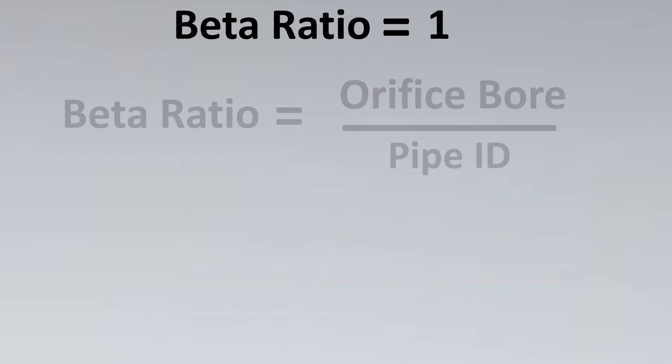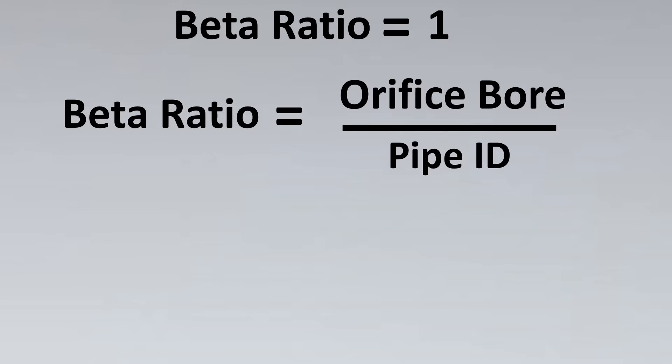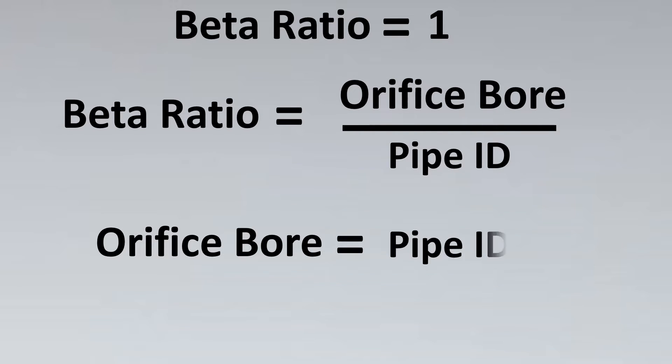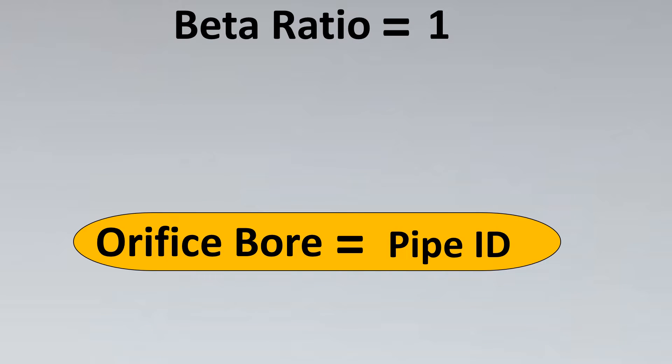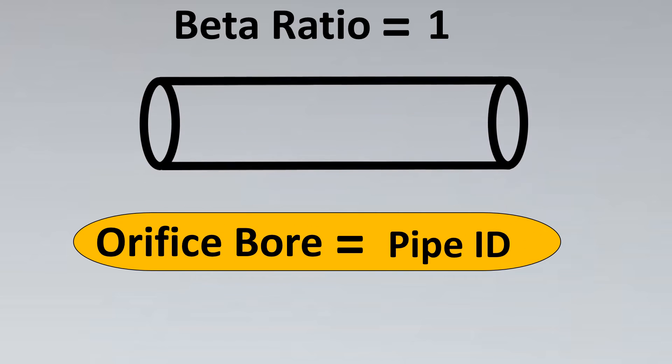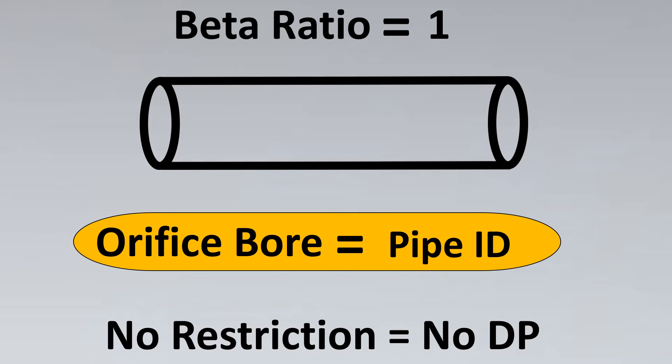Now let's get to the interesting part. Let's try to explore and find out what if we don't follow this. What happens? Let's keep beta ratio as 1. If we keep beta ratio as 1, as per the formula, the orifice bore has to be equal to pipe ID. Then they would cancel each other, the answer would be 1. So if we keep this the same, what is going to happen is you would have absolutely no restriction to the flow. So there would be no DP. So we can surely not keep a beta ratio of 1. That's absolutely out of context.